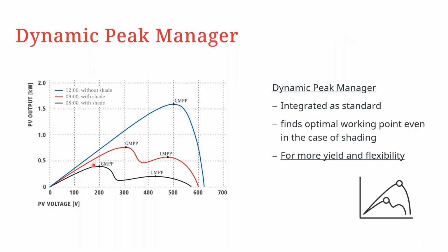To give a better illustration of this, we can look at this curve where we have 3 instances in the production. One curve is during midday where we have no shading at all, and therefore we can reach a very good maximum power point, which we are referring to here as the global maximum power point. Then we have another curve, 9 in the morning with a bit of shading. With a bit of shading, it's possible that we have at least 2 maximum power points. One is what we refer to as the global maximum point, and then we have another one that would be the local maximum power point.